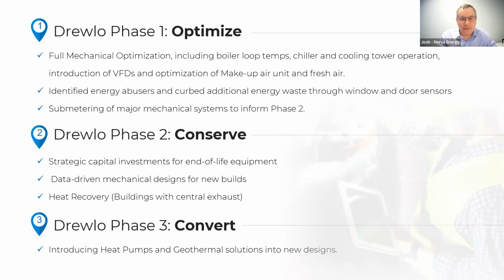That can't be tolerated. It's a waste. It doesn't provide really good comfort in the end, but people operate that way. And I really feel it's subconsciously because they're not putting a value on that heating or cooling because they're not paying for it. Therefore, certain people will abuse it. Well, as part of the optimization step within these buildings, that abuse has been curtailed primarily through the identification of the abusers through the data, and then the installation of window and door sensors, which essentially prevent a tenant from running their heating or cooling while the window or door is open in order to prevent that waste. Also included in this step is the submetering of the major mechanical systems to inform the phase 2.